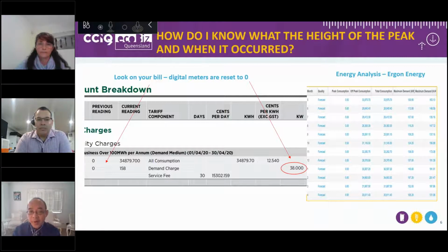So this is the chargeable demand component, not the actual demand. The actual demand, for this instance, if it's tariff 44, is 68 kilowatts, but once you take off the demand threshold of 30, so the first 30 kilowatts you're not charged for, you are charged for 38 kilowatts. The other thing to point out in relation to your bill is to understand whether you're on a digital meter or not, and therefore may be charged kVA from 1st of July 2020. In the previous reading section, it has a figure of 0. Digital meters are reset to 0 for each billing period, so that's another sign that you can see whether you have a digital meter or not.